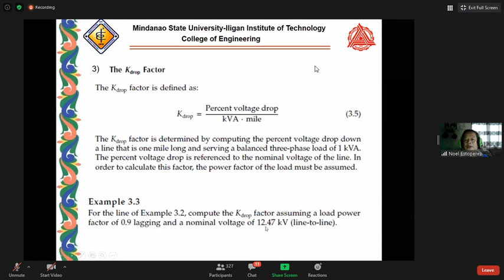Now, for example, we want to compute the K drop factor assuming a load power factor of 0.9 lagging and a nominal voltage of 12.47 kV line to line. So the impedance of 1 mile will be computed, because earlier that was in ohms per mile. Times 1 mile, we have 0.306 + j0.6272. And the current taken for 1 kVA at 0.9 lagging power factor with the nominal voltage of 12.47 kV is 0.046. The voltage drop can be determined from the real part of the impedance times the current. So this is now the voltage drop. The nominal line-to-neutral voltage will be 12,470 over root 3.